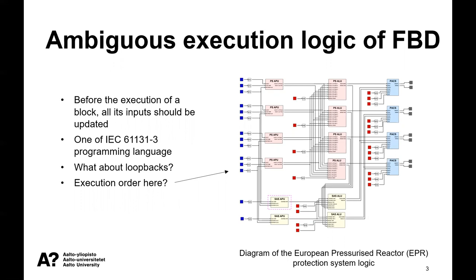However, this requires from an engineer an additional thought on how to place those function blocks in those networks in order for them to be executed correctly. And this process is quite error-prone, because even if the blocks are not placed correctly, they can be executed, and such execution may result in non-obvious mistakes. Basically, at some point, maybe not even from the beginning, there will be a mistake and it will be very difficult to find. And in the end, it will lie in the execution order.